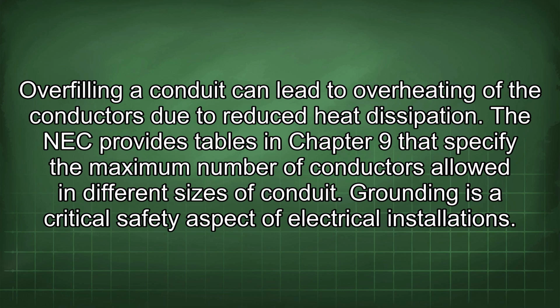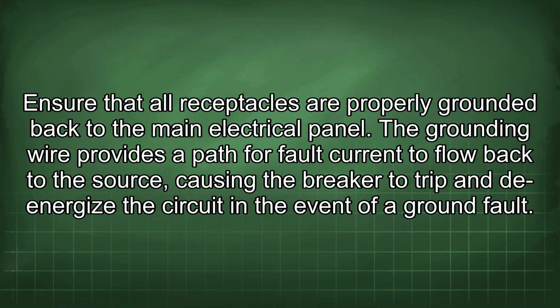Grounding is a critical safety aspect of electrical installations. Ensure that all receptacles are properly grounded back to the main electrical panel. The grounding wire provides a path for fault current to flow back to the source, causing the breaker to trip and de-energize the circuit in the event of a ground fault.